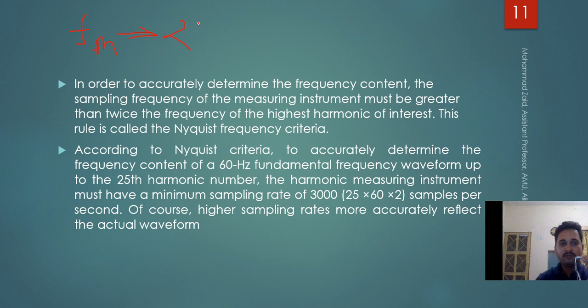So what does the sampling theorem tell you? It tells you that first you decide what is the maximum frequency which you are going to measure. So maximum frequency F max will depend upon the maximum harmonic component which you are going to measure. For example, in my case it is the 25th. The 25th harmonic will correspond to a frequency of 1500 Hertz. So I need to sample my waveform at a frequency of minimum 3000 Hertz.